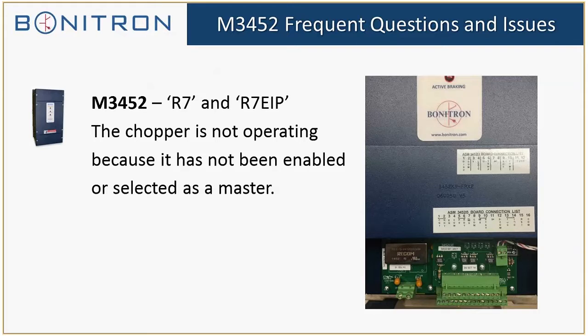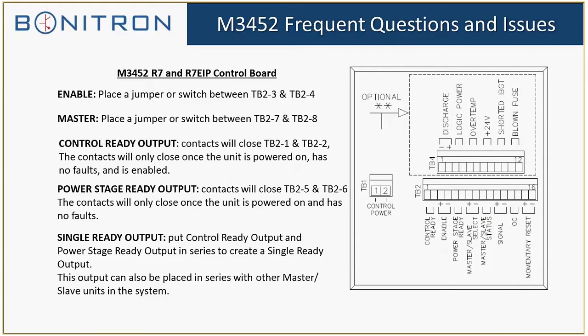This is the detail of the actual physical unit. Underneath the lower panel, which I took off for this picture, we have a small little cheat sheet that basically describes where the enable is, where the control ready output signal is, and the power stage ready output signal is. This is very small, almost a code, so it's really best just for the customer to look at the manual. This has a better description. In the next slide, I actually just did a screen grab of the actual drawing in the manual.